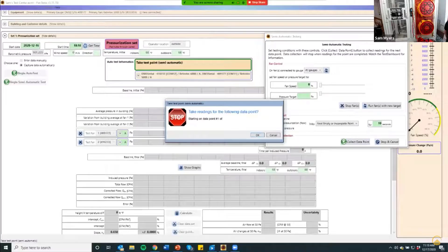So I've got my 0% in here. I'm connected to all the gauges, and I want to do an initial baseline. So I'm just going to tell it to run fans to that target. And if I move over here and tell it to collect that data point, it's going to start to collect.